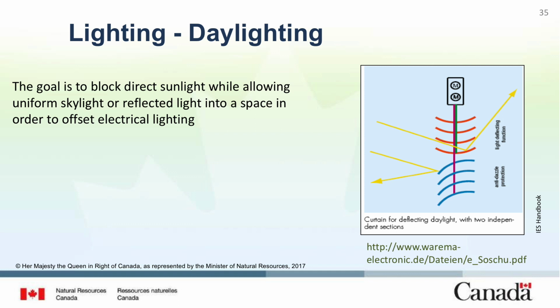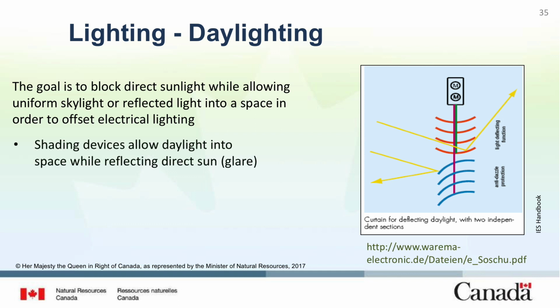One of the most common mistakes is putting in daylighting controls, but then having no way of controlling direct sun in the windows. So the occupants will close the blinds, and then the daylighting controls don't do anything. So the first step in correcting using daylighting is to make sure that you have redirective devices that are controlling glare in the space and allowing direct sunlight in at some level.